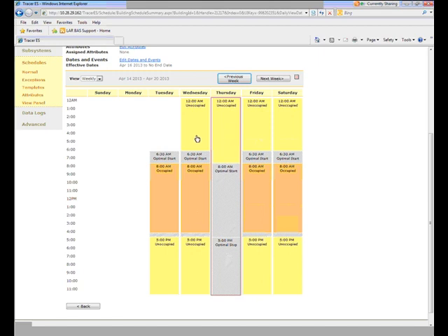But basically you can see how different the exception looks. You get an outline around the particular date that you make the exception for, and it looks different from all the other events. In this case right here, we had all the other events starting at 6:30 for the optimal start and then going occupied at 8 a.m. and then the optimal stop at 4:30 and the unoccupied at 5 p.m. For some reason when I clicked, I must have clicked wrong and my times didn't take correctly on the exception. Questions?